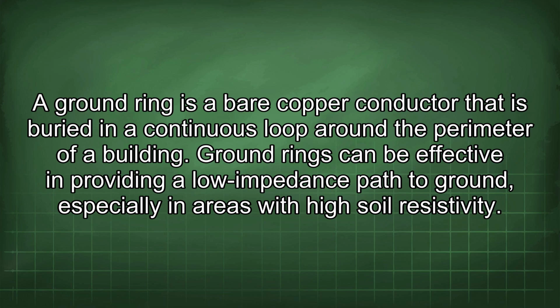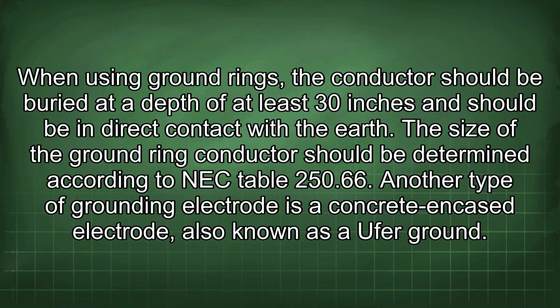A ground ring is a bare copper conductor that is buried in a continuous loop around the perimeter of a building. Ground rings can be effective in providing a low impedance path to ground, especially in areas with high soil resistivity. When using ground rings, the conductor should be buried at a depth of at least 30 inches and should be in direct contact with the earth. The size of the ground ring conductor should be determined according to NEC Table 250.66.